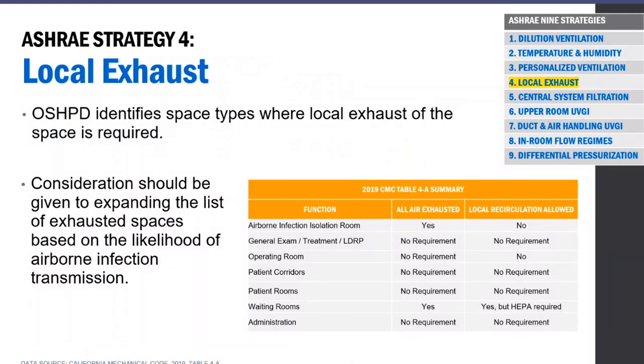So again, this is a summary of the 2019 CMC Table 4A, which identifies the spaces. This is a summary of the table, but it identifies the airborne infection isolation rooms. All air is exhausted to the outdoors with no allowance for recirculation within the space to control infection. Similarly, waiting rooms within hospitals are to be exhausted, but they do make an allowance for recirculation if HEPA filtration is applied.